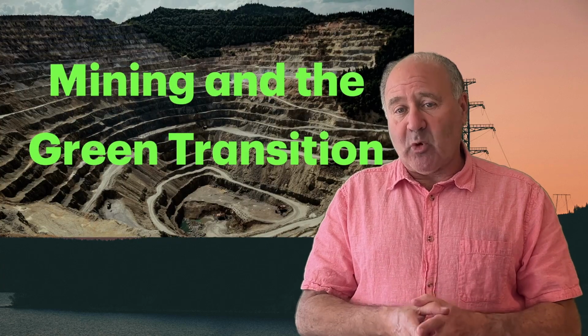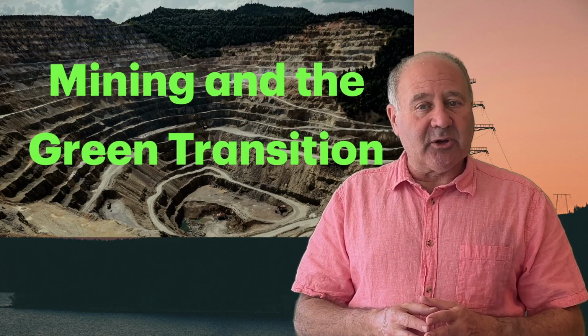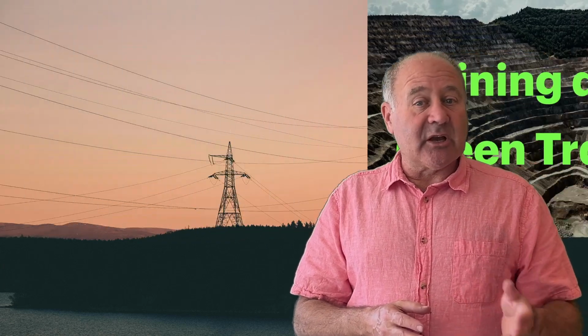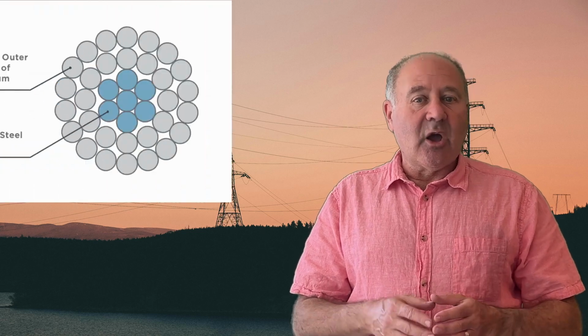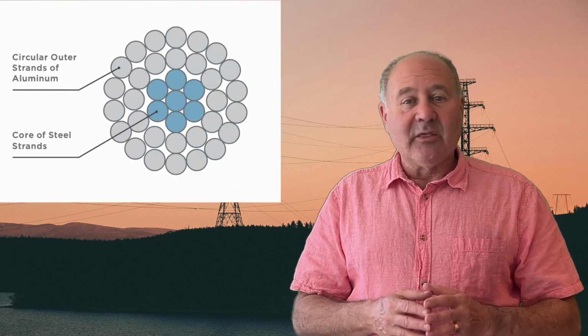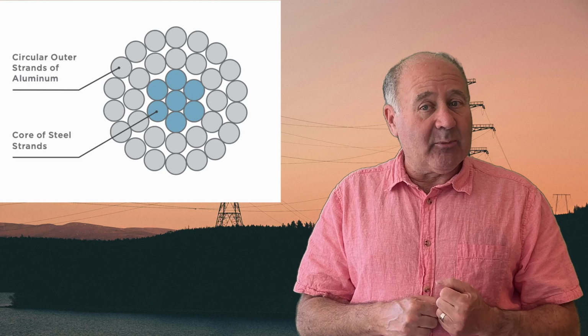When I think of a conductor, copper is what comes to mind. But as was discussed in the episode on mining, aluminum is much more plentiful and is a pretty good conductor. The most common conductor for high voltage power transmission has been the aluminum conductor steel reinforced cable, featuring conductive strands around a steel core. This provides the strength to support the cable.